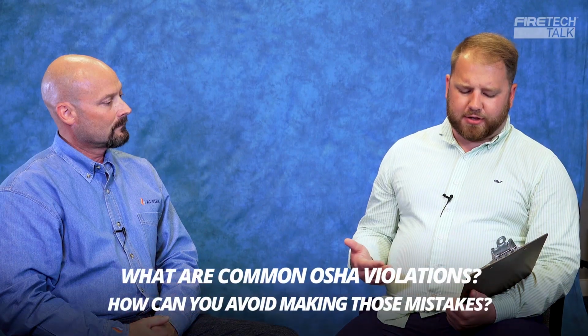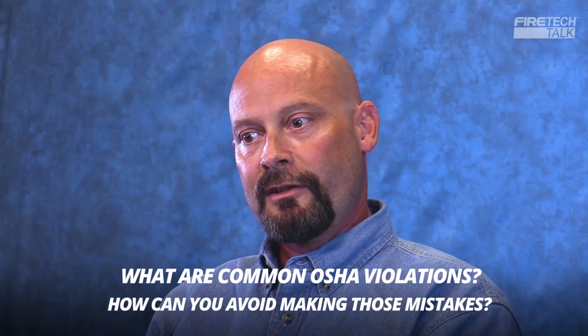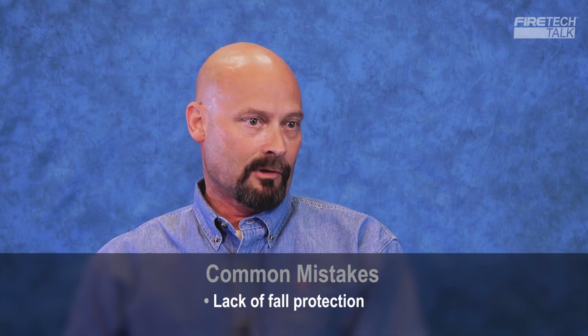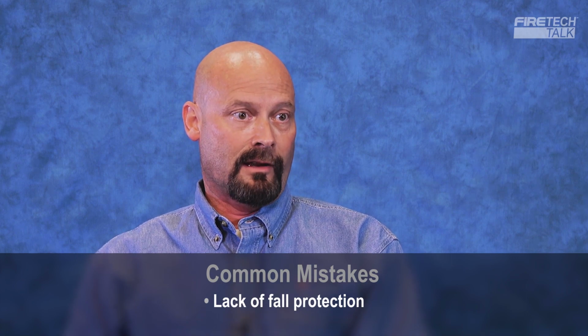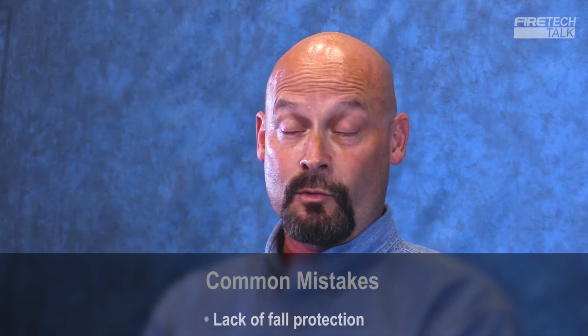What are some common OSHA violations in the fire safety industry, and how do you avoid making those mistakes? In the fire protection industry, we see probably more slips, trips, and falls. The other thing that we will see is lack of fall protection. Those are some of the big fines that you'll find. OSHA just recently for 2019 raised their fines from about $7,000 or $8,000, $12,000, excuse me, to about $13,600 for a serious violation. It can go up to $132,600 for a willful violation. So if they find that you knew or that you should have known about the hazard and failed to protect your employee, you could be hit with a willful violation of upwards of $132,000.